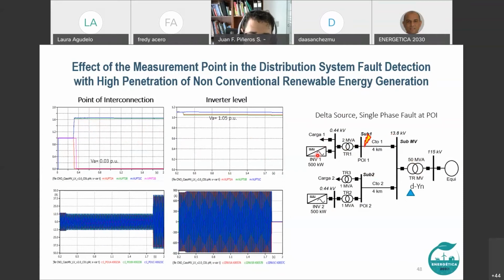But in the low voltage functions at the inverter level, you cannot see that. This is because of the connection, of course, the vector group and the delta system. If you don't have a measurement point and a function connected to that measurement point, you will not be able to detect it, and the inverter will not realize there is a problem.